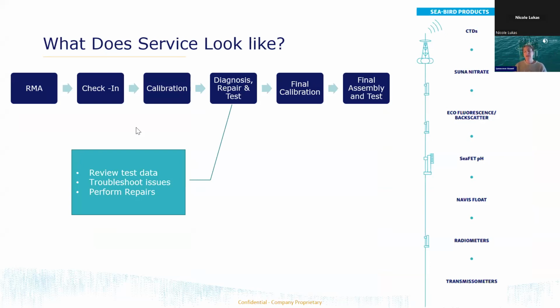They're interpreting those results and determining, are all the sensing components working the way that they should? Are they drifting the way that they should? And then making any repairs that need to happen. They may also be conducting specialty tests. So in certain scenarios, we may have a situation where an instrument is behaving in a certain way in the field, and that may look different than the tests that we typically perform in our lab. So occasionally we have to perform extra tests to be able to stress the instrument in the exact way that the customer says is potentially causing the problem.